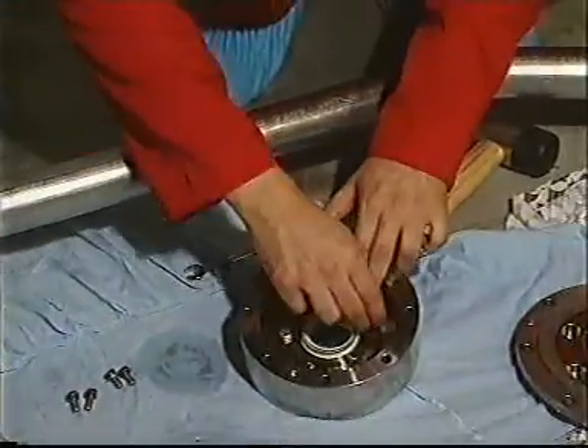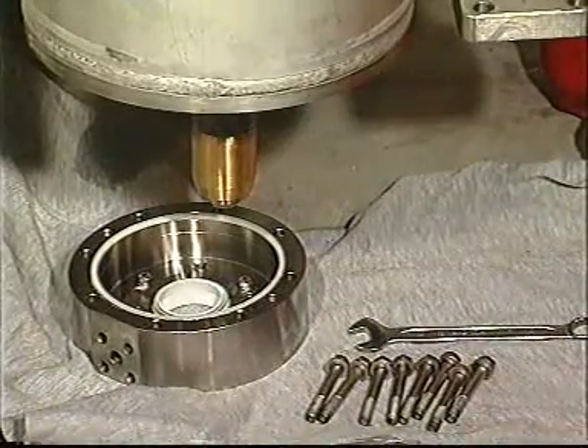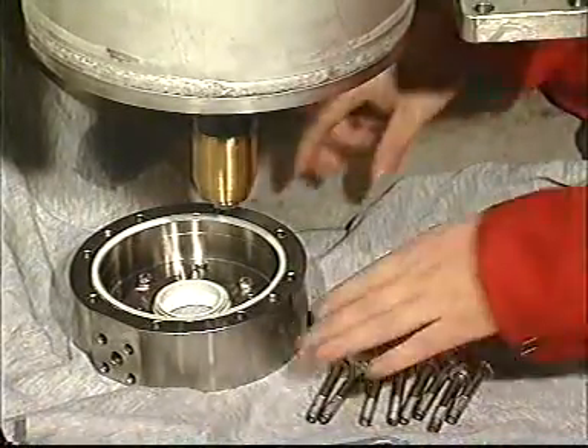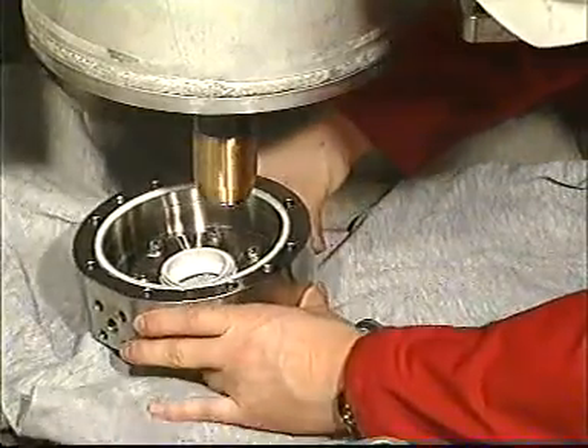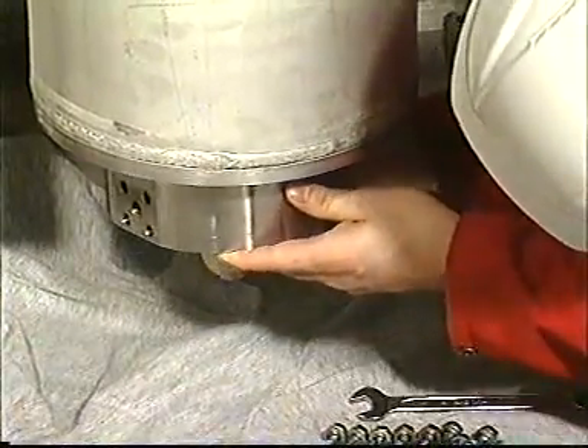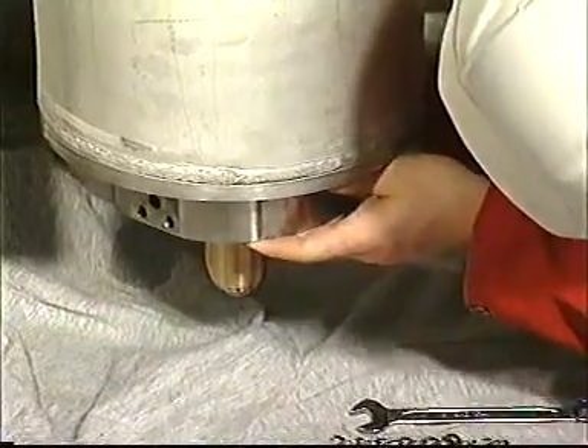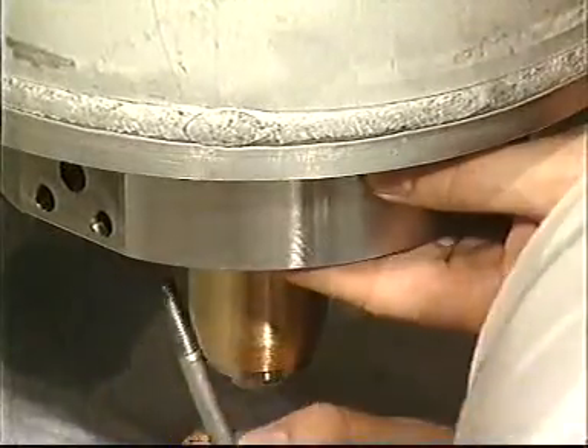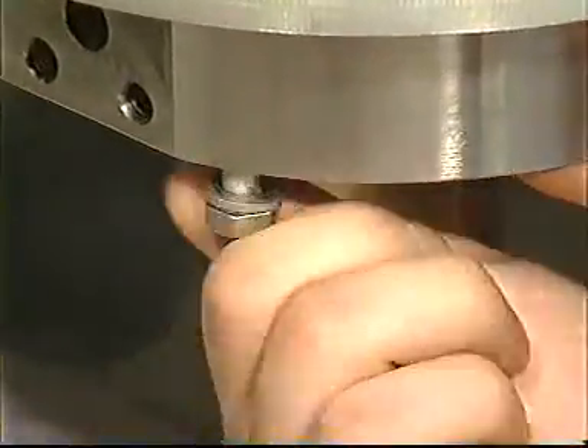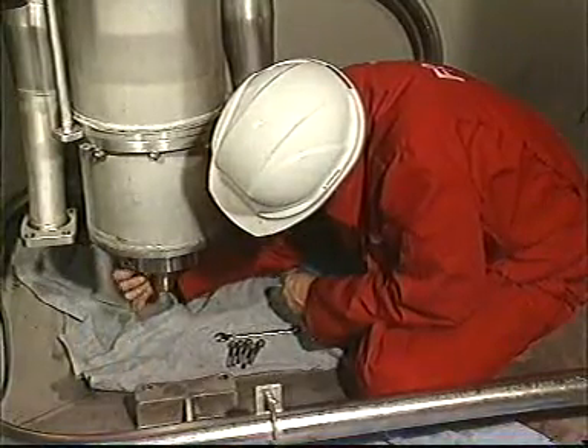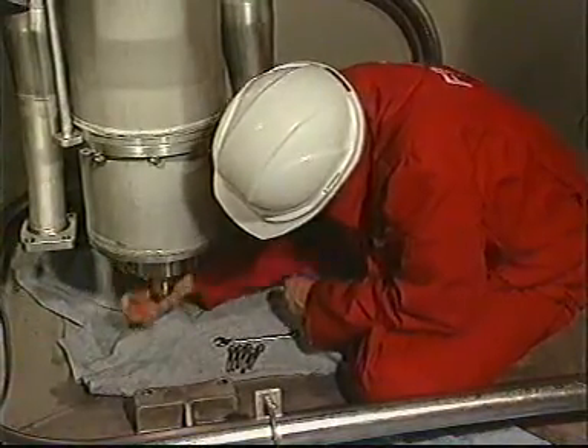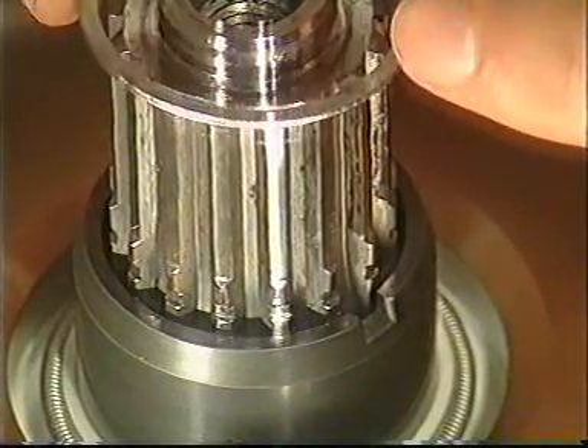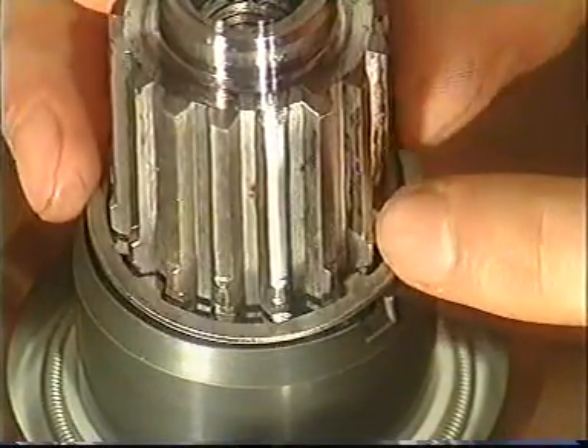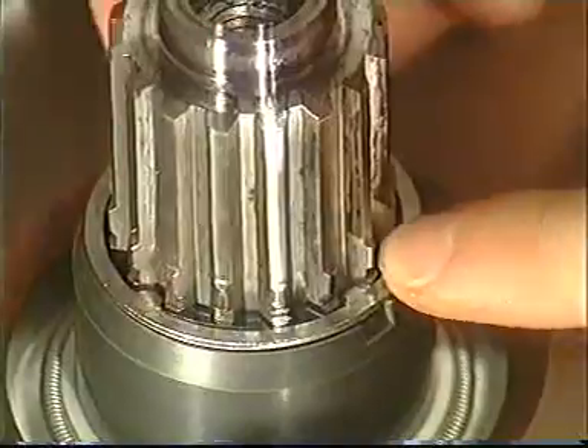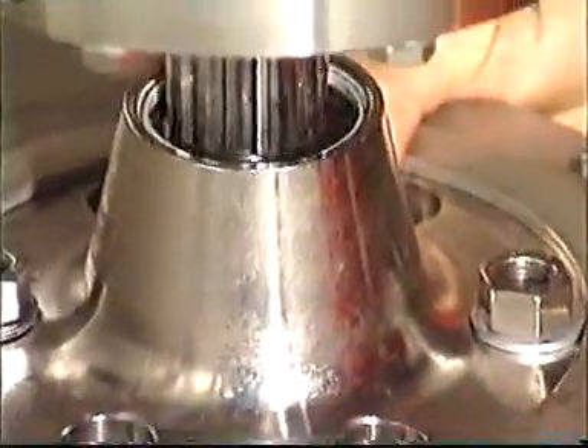Check all seal elements, seal grooves, and seal faces carefully. Pay special attention to the Teflon rings and be absolutely sure of no deformation. Never install a damaged O-ring and be sure of no corrosion, cracks, dirt, etc. And remember, use only genuine spare parts. Also pay attention to how to fit the retainer ring in the right position, at the end of the ceramic sleeve and in position on the splined shaft.